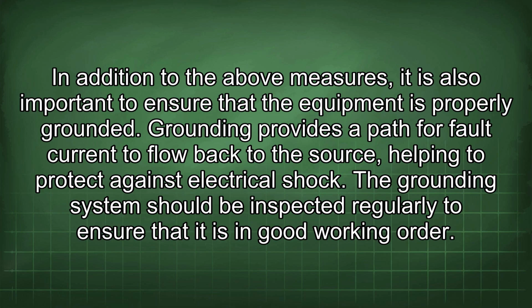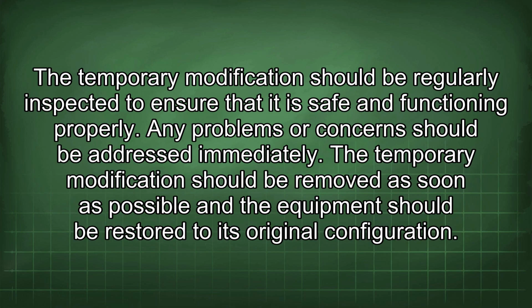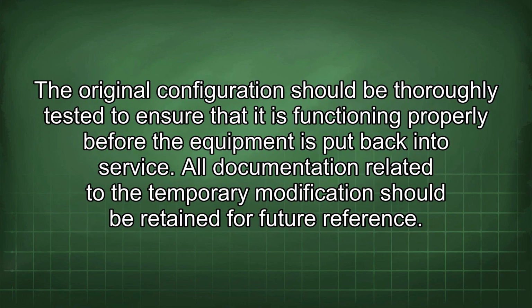In addition to the above measures, it is also important to ensure that the equipment is properly grounded. Grounding provides a path for fault current to flow back to the source, helping to protect against electrical shock. The grounding system should be inspected regularly to ensure that it is in good working order. The temporary modification should be regularly inspected to ensure that it is safe and functioning properly. Any problems or concerns should be addressed immediately. The temporary modification should be removed as soon as possible and the equipment should be restored to its original configuration. The original configuration should be thoroughly tested to ensure that it is functioning properly before the equipment is put back into service. All documentation related to the temporary modification should be retained for future reference.